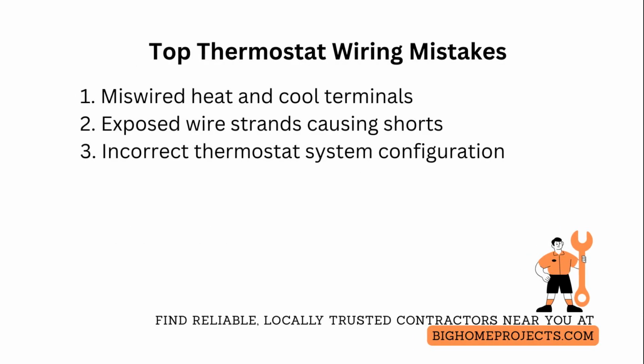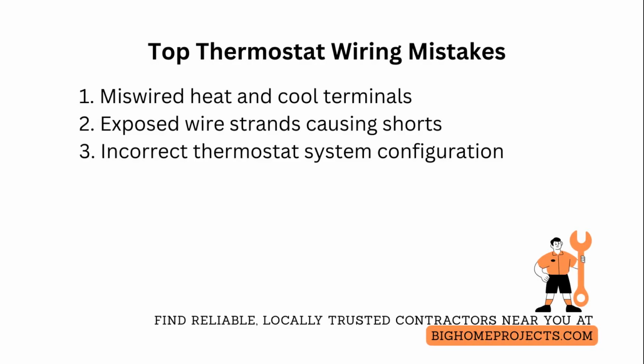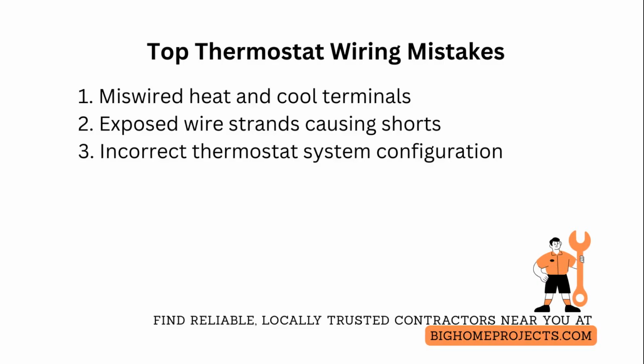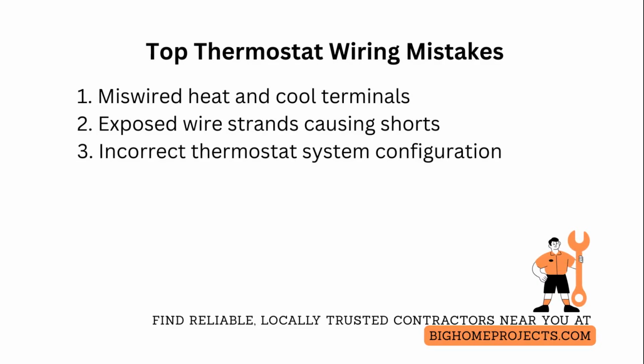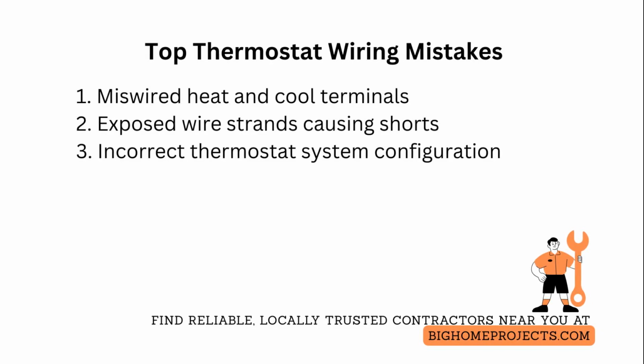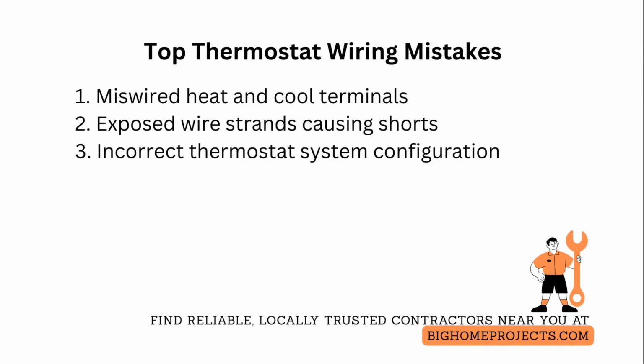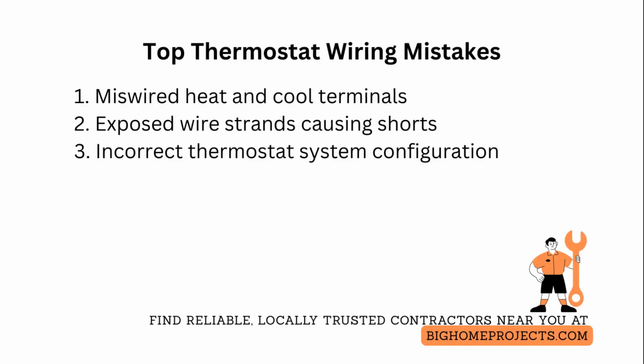One of the most common thermostat installation mistakes is miswiring the heat and cool control terminals, which causes continuous operation. Fix it by matching terminal letters precisely and testing continuity so there are no cross connections. One of the top issues is leaving wire insulation too long, so stray strands create a short. Remedy this by restripping to a clean 1/4 inch and tightening screws securely while checking for exposed copper.